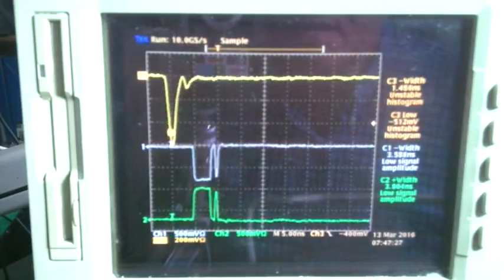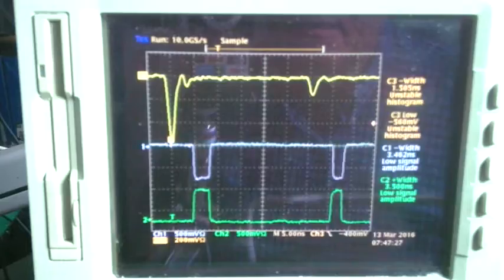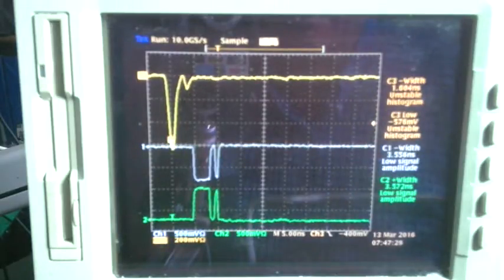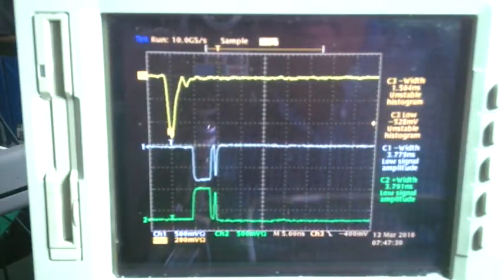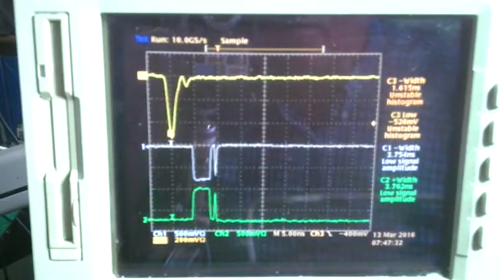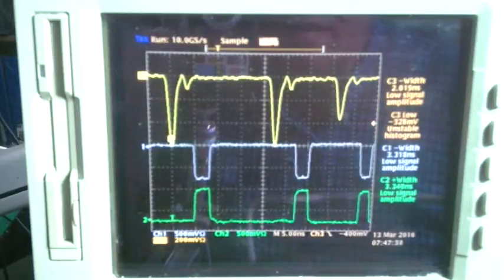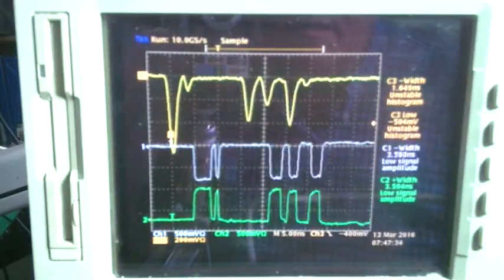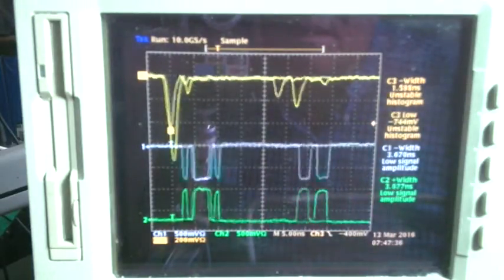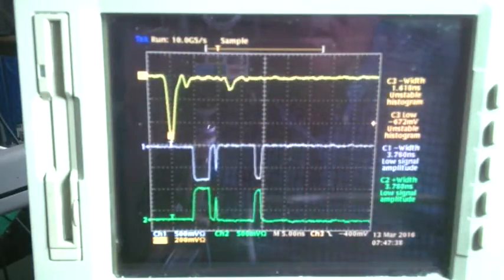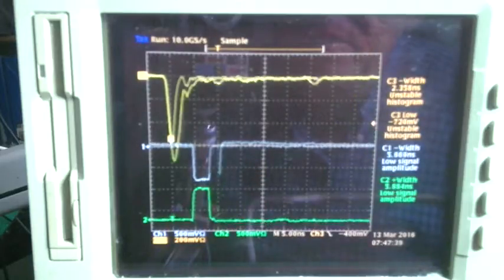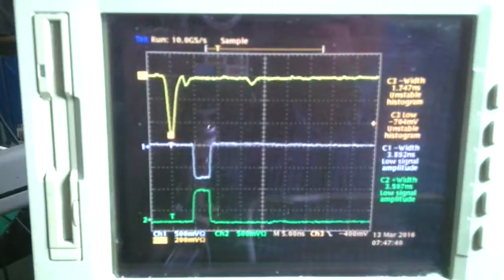And occasionally a little bit of after pulse or pulse width increase caused by ringing on the photomultiplier tube.